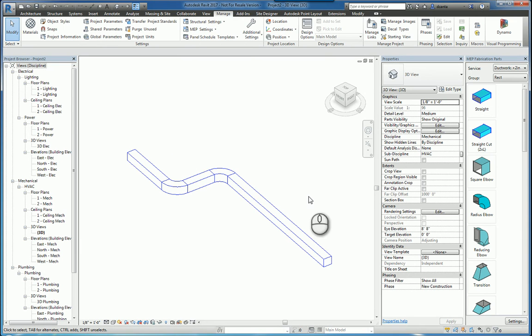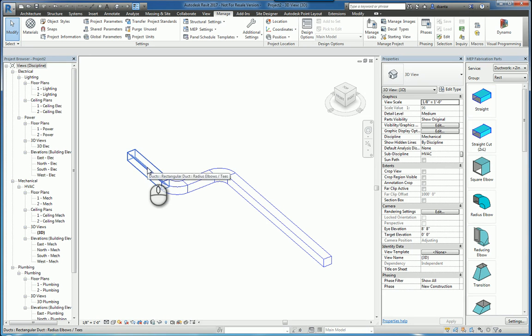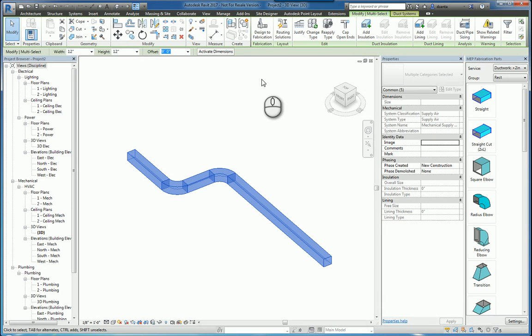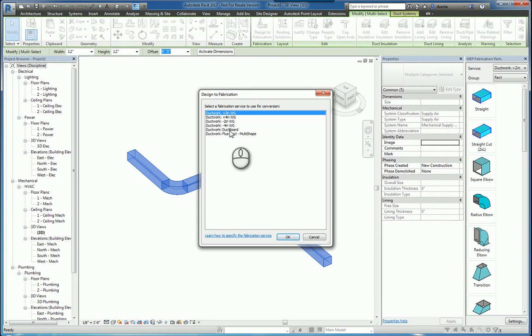If you've designed your Revit model MEP systems with the standard content, you can actually switch this content to fabrication content without actually having to manually draw them using the library given to you. For example, I can select either a duct, or I can hit Tab and select the entire system, and I'll get a contextual tab called Modify Multi-Select. In here, you'll see the Fabrication Panel, and you can click Design to Fabrication. It'll ask you which particular service you want to work with — you select what you need and click OK.